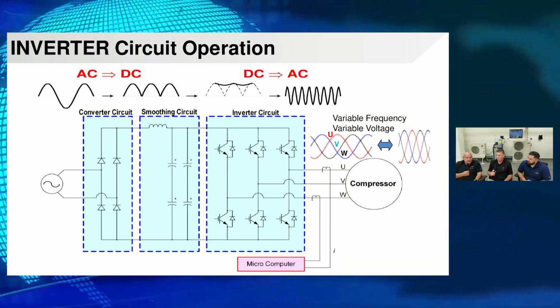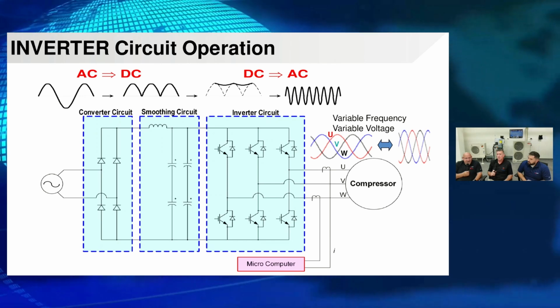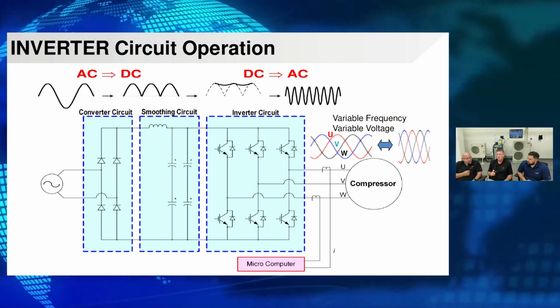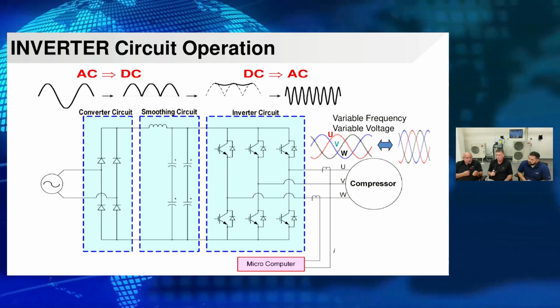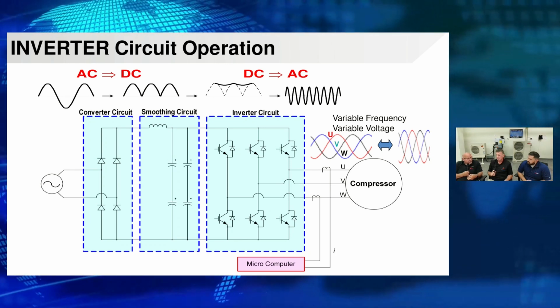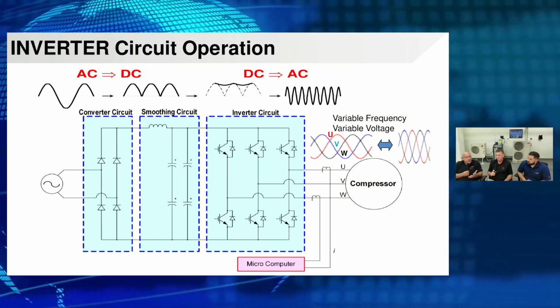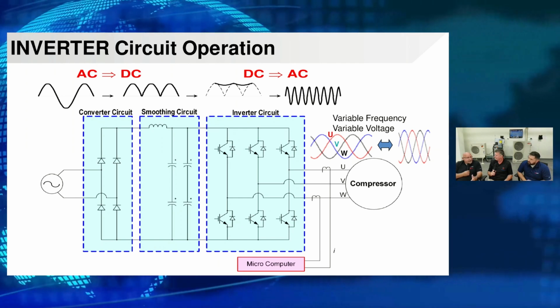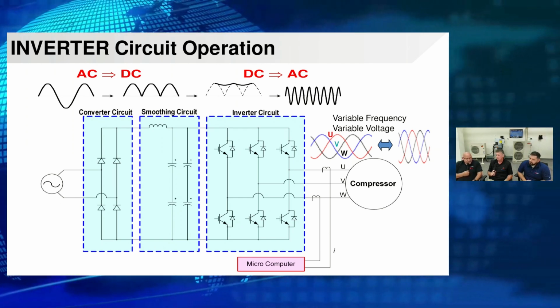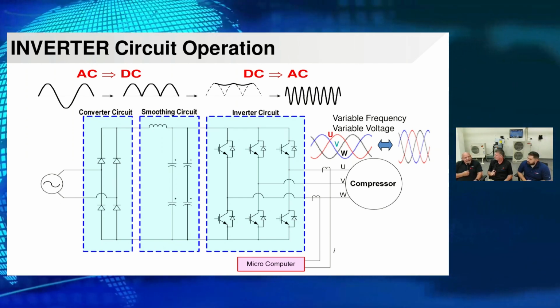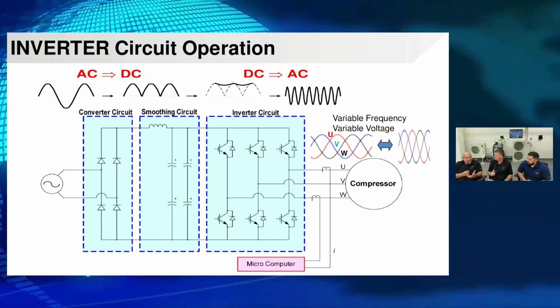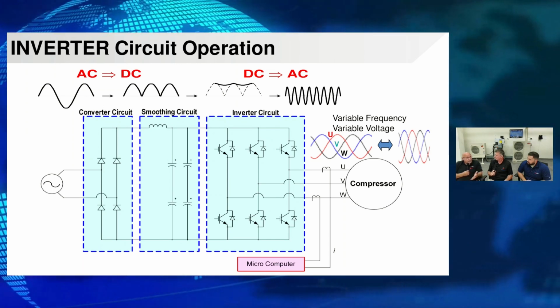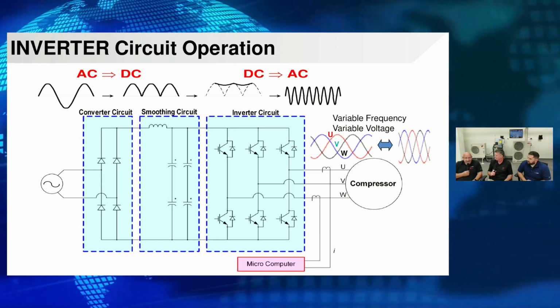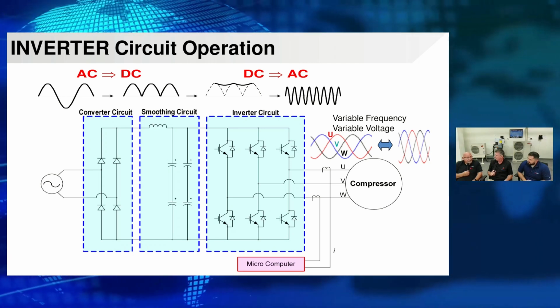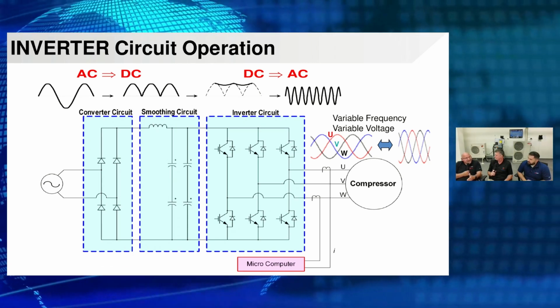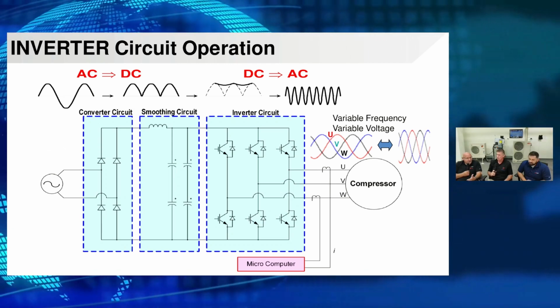Okay. Another thing you see in this design is a microcomputer. And all it is, is two chokes where two wires go through. And that's what I call my amp probe. So I'm monitoring what's happening. Yes. Very true. And I get a lot of technicians asking me, well, can I check a locked rotor compressor with my amp probe? And I said, you won't see it in an inverter circuit. No, not at all. Because the inverter will see it a lot quicker than the amp probe will. So you won't be able to see it.